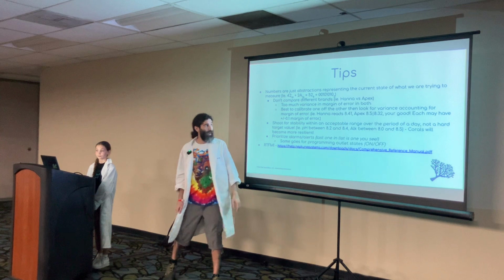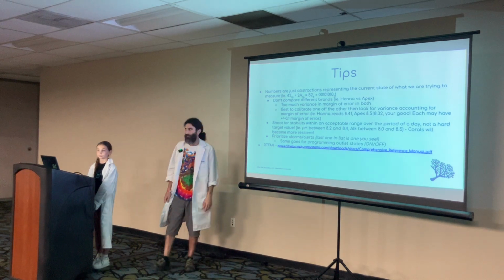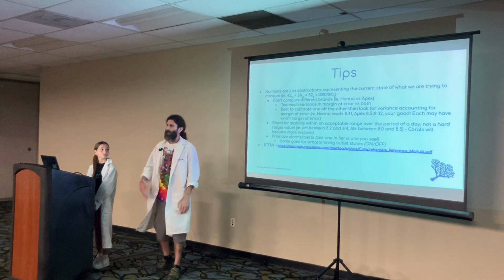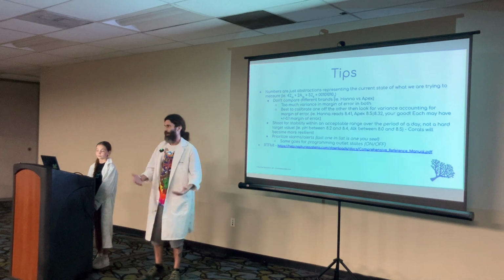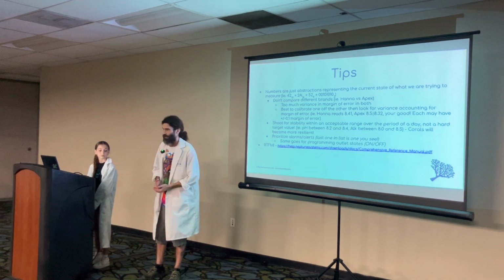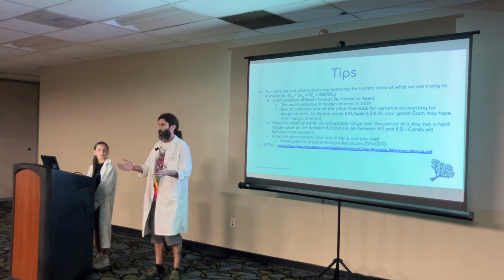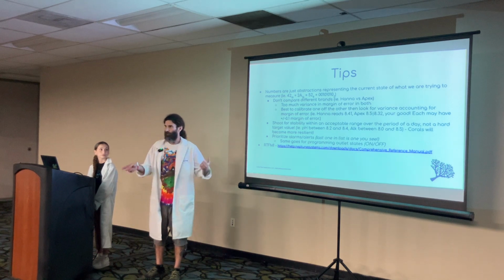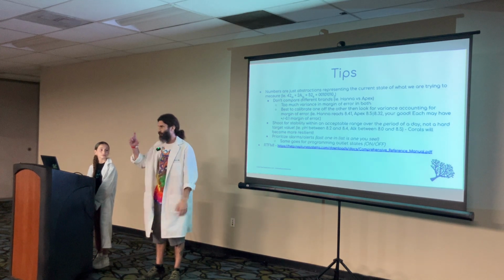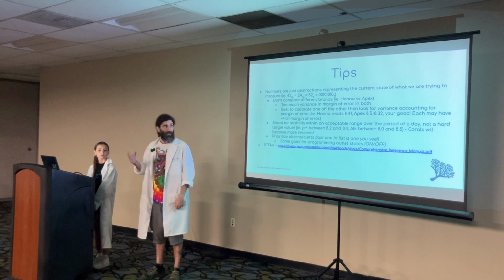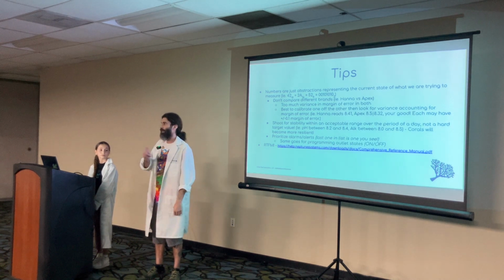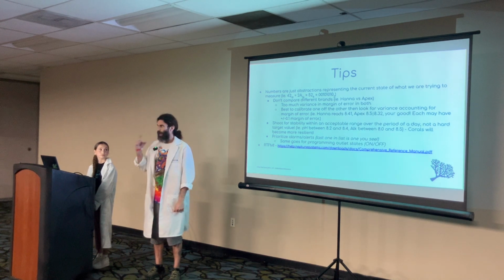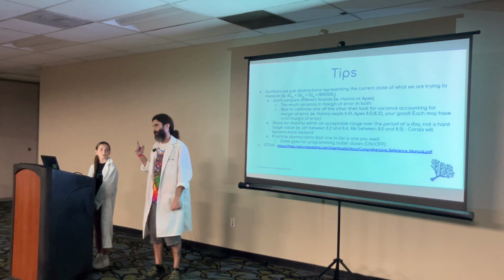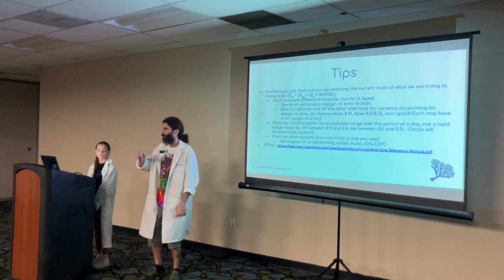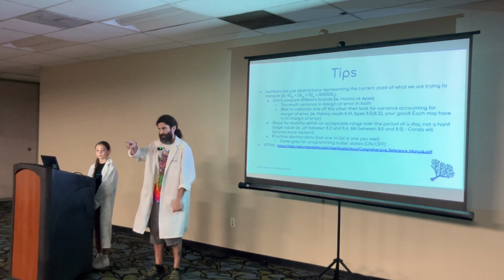Don't compare different brands, right? We hear so much of Hanna versus Apex. My Apex is not reading the same as my Hanna. My Trident doesn't read the same alkalinity as my Hanna does. They're not gonna. They never will unless you calibrated the Trident to the Hanna rather than using the calibration solution they gave you. And that's what I do. I calibrate my Trident to my Hanna, right? And then I use a reference solution on the Hanna because you can't calibrate the Hannas. So you buy the reference solution, which gives you the margin of error you're currently running at, right?